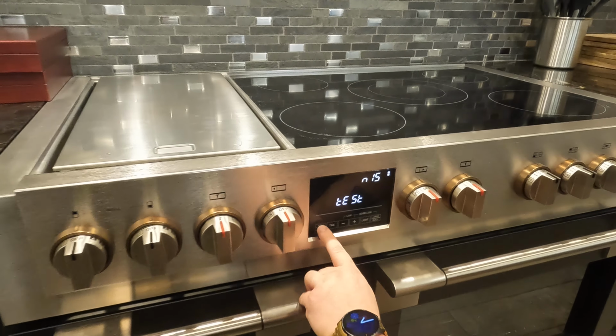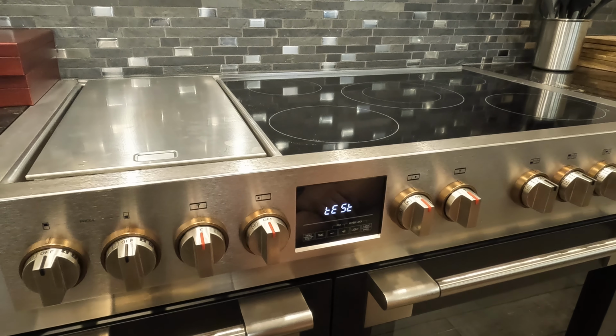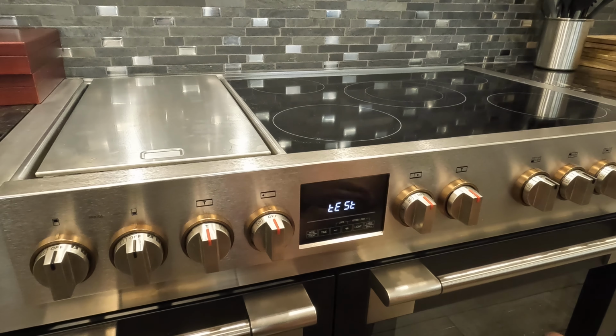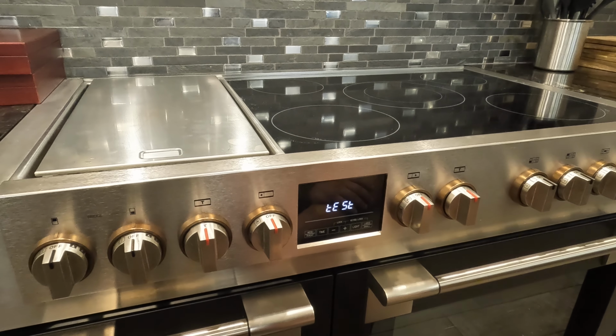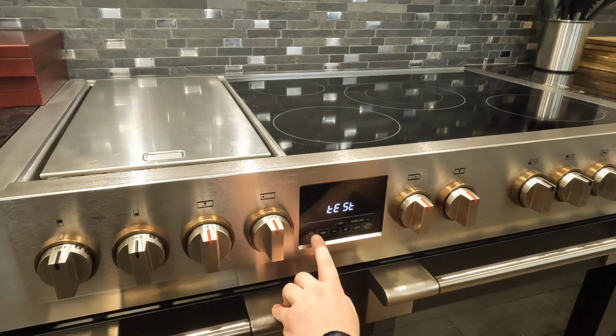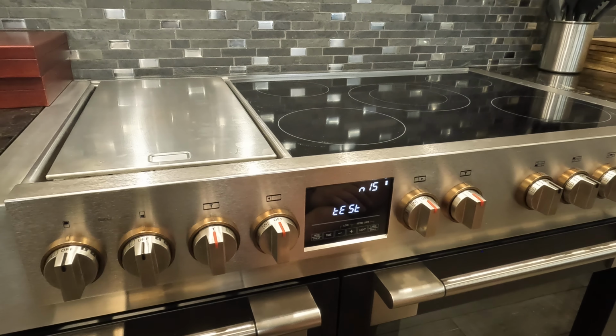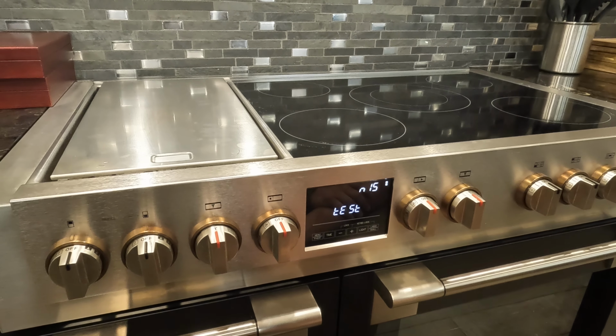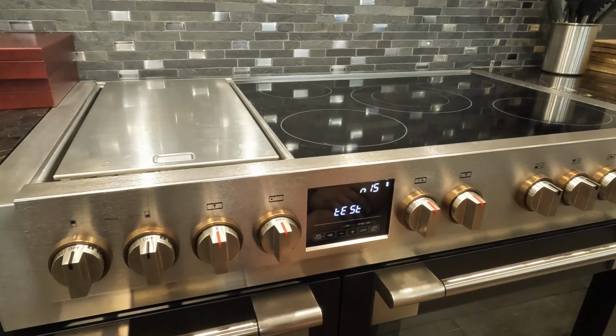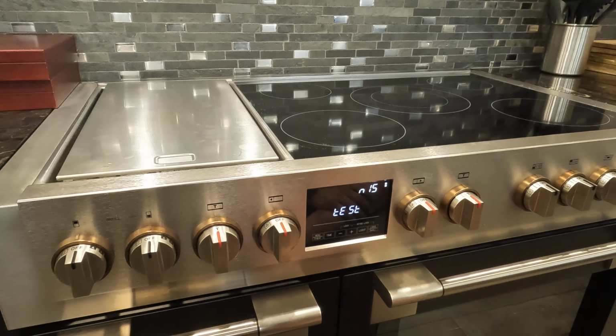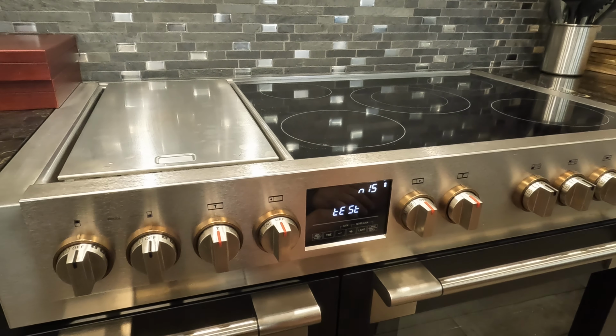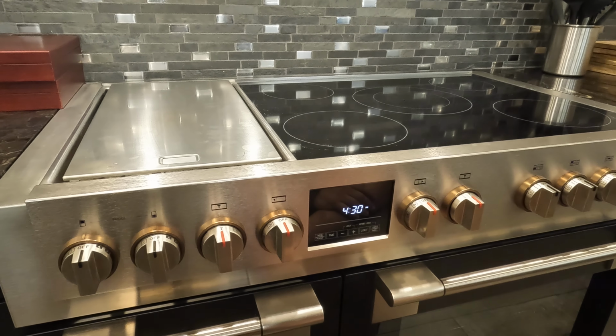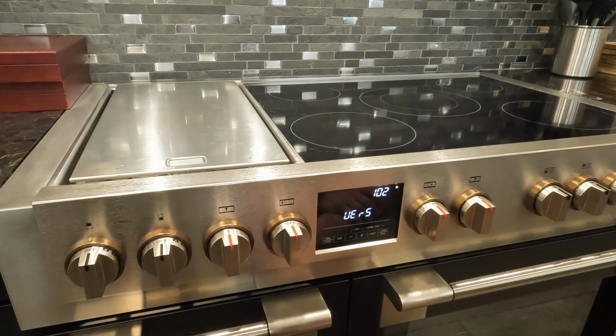On this window, I'm going to press menu 1 time. You'll see that N15 begins to flash. This will allow me to change the software selection. Once I've made my selection, I will press menu again. You'll see that it goes back to solid. Give it a few seconds and the menu is going to reset.